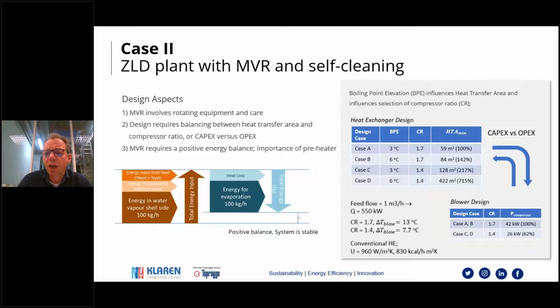If I then look at the difference in compression ratio, for example, with the same boiling point elevation, so comparing A and C, you see that for the same boiling point elevation, when I reduce my compression ratio, because I want to use less energy during the runtime, my heat exchanger does not need to be 100%, but I need to go to 217%. So you see, I can go to a lower energy consumption over time, but then I need to increase my heat transfer area. Case by case, with customers, we can see what is the most optimal for their case, but it's really important to realize that you're always balancing between investment and operational cost.